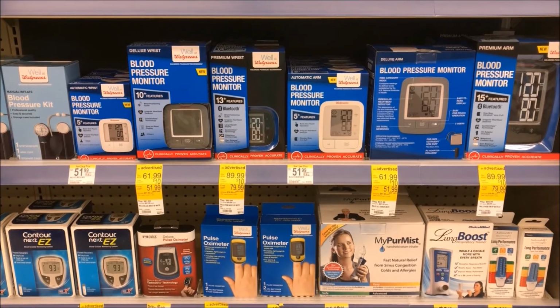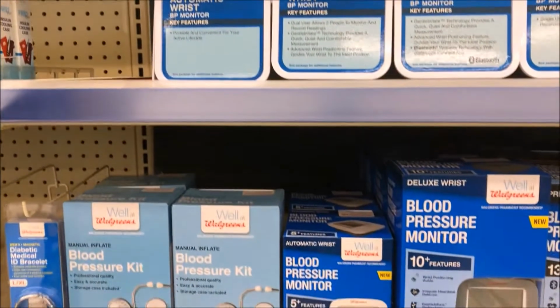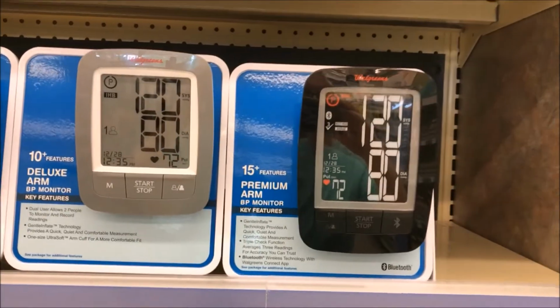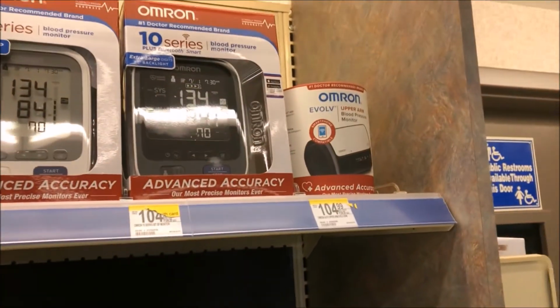Algorithms are designed by blood pressure monitor manufacturers to estimate blood pressures. Different manufacturers develop different algorithms that are proprietary. There are many variables that affect the validity of individual blood pressure estimation, including arterial compliance, blood pressure level, arm composition, and arm shape.